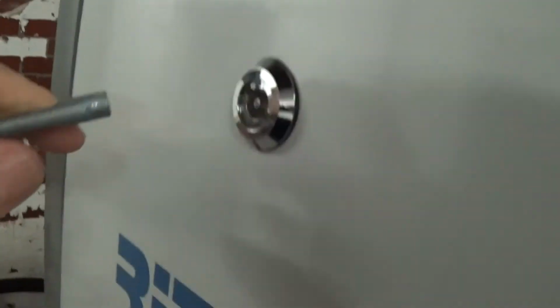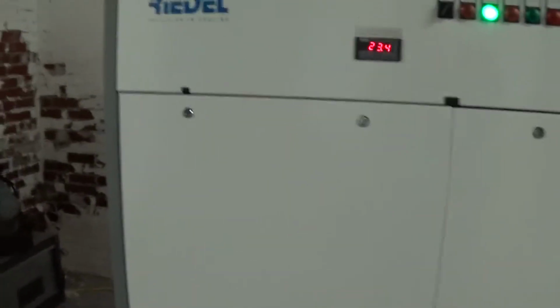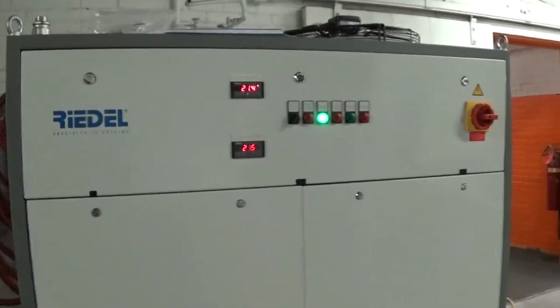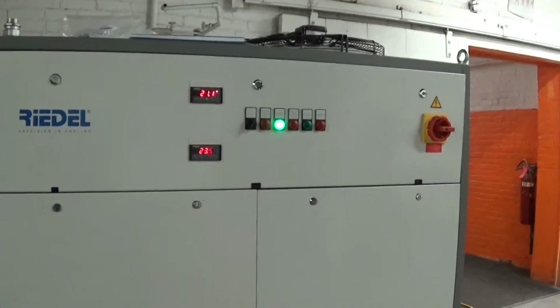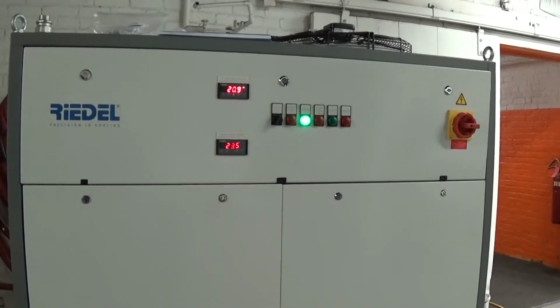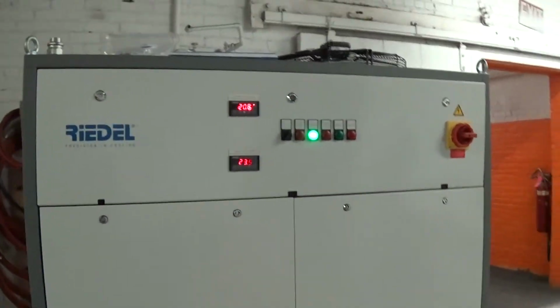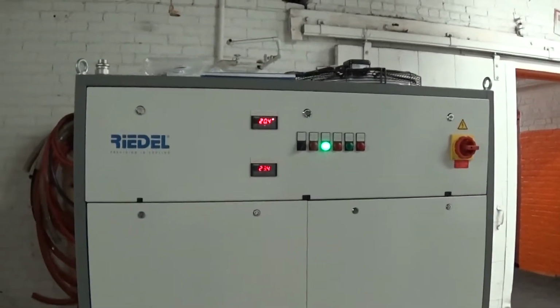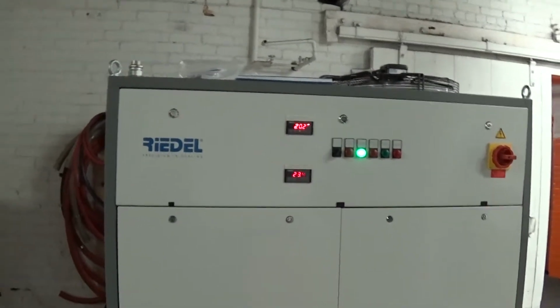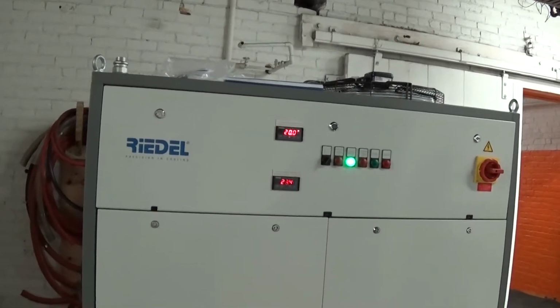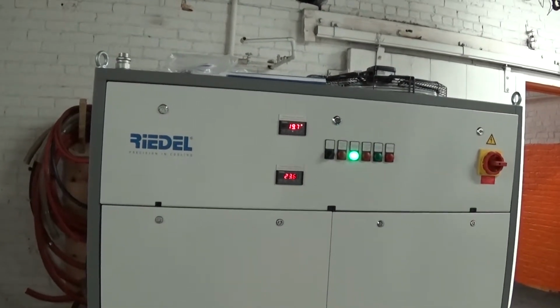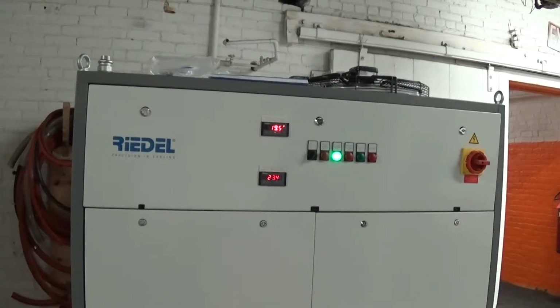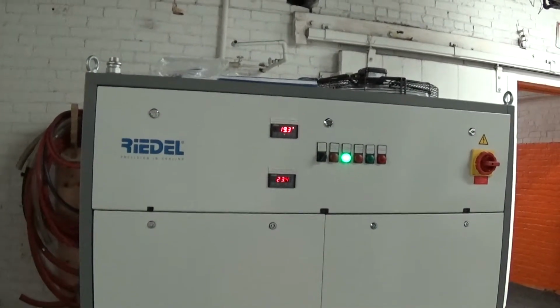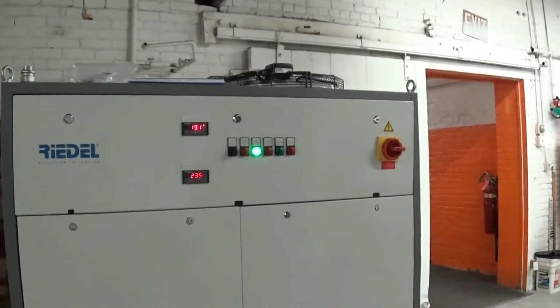Earlier I showed you, obviously we got 2 compressors for staging, and depending on how quickly we're cooling and the temperature, the controls will dictate what compressor comes on when. In our scenario here, we have a very little load, but we also have that hot gas bypass in there, so our differential is actually going to be plus or minus 1. So if, like for this here, we set it to 15 degrees C, it's not going to turn back on and start cooling till it reaches 16. And it's not going to turn off till it reaches 14.